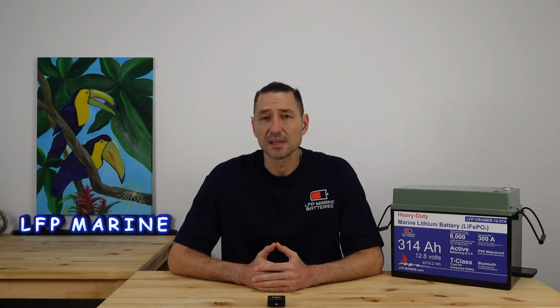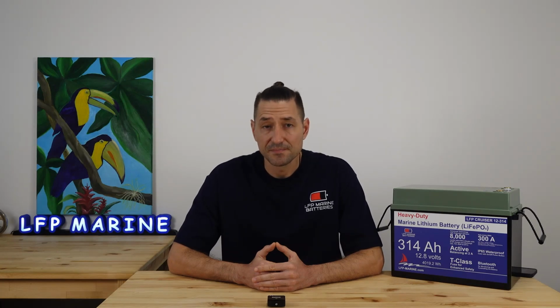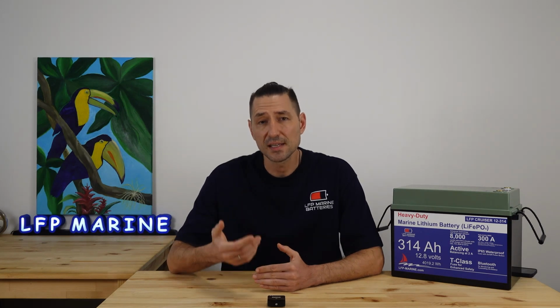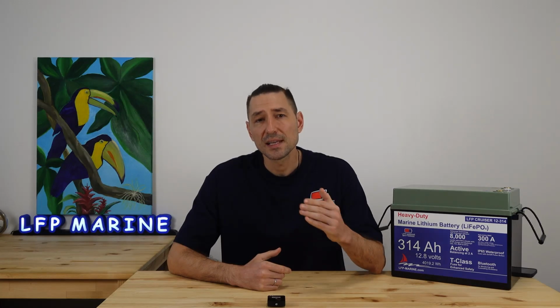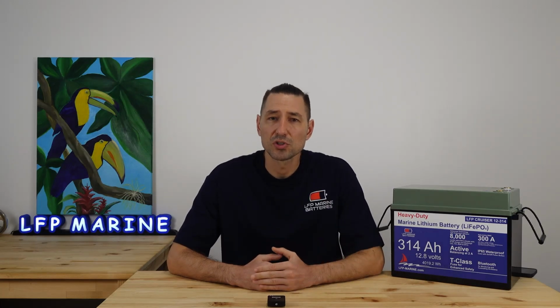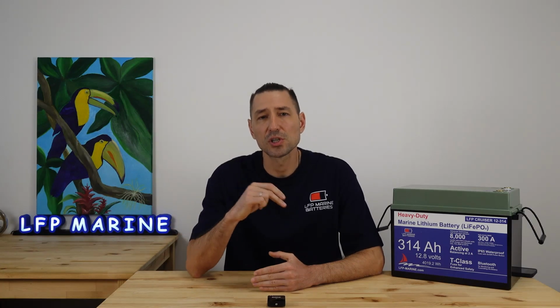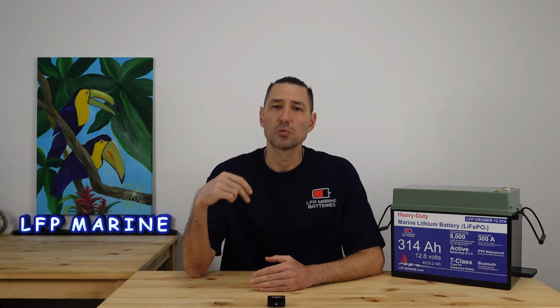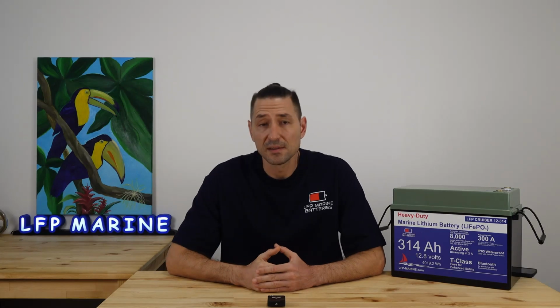Second, in high ambient temperatures, it's absolutely critical to minimize heat generation inside the enclosure because higher temperatures reduce the battery's cycle life. To reduce heat generation, we use cells and a BMS with low internal resistance. We also increased the cross-section of all wires and connecting elements inside the enclosure by 30%. We use the active balancing method, where cell voltage equalization is achieved by redistributing current rather than dissipating heat through resistors as in the passive balancing method.